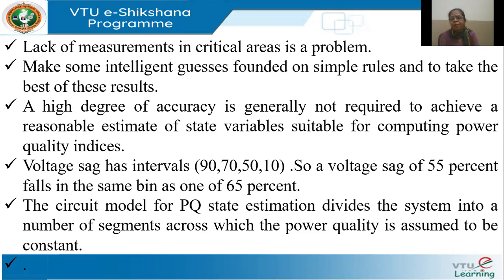Now, a very high accuracy is not needed, because you remember when we saw the thresholds for voltage sag, for example, the thresholds were 90, 70, 50, 10. We discussed why all these thresholds have come. If I have a sag of 55% or 65%, both will fall in the less than 70 category. What do I need? I need to know whether the sag falls within the category less than 90 or less than 70 or less than 50. I don't need to know exactly whether the sag is 55% or 65%. Clear? So I don't need an exact estimate. Accuracy is not of much importance, because the thresholds have a wide range.